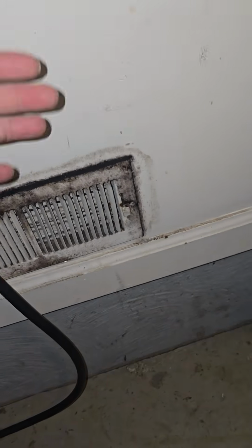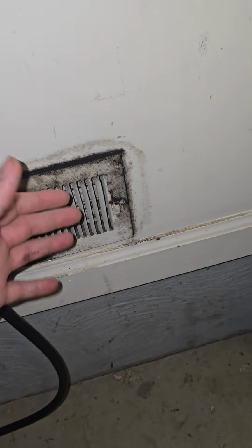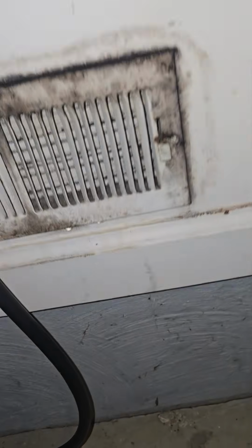So here in summer, where air is coming into this garage, but it can't effectively go back in, this garage will never be cool. It will always be hotter than the rest of the home. Might be a little bit cooler than the outside, but it'll always be pretty warm. And when you have this warm garage and this cold air at the ducts, you have a big temperature difference, which increases the chance of condensation occurring.